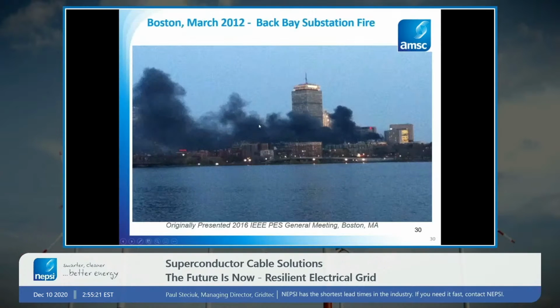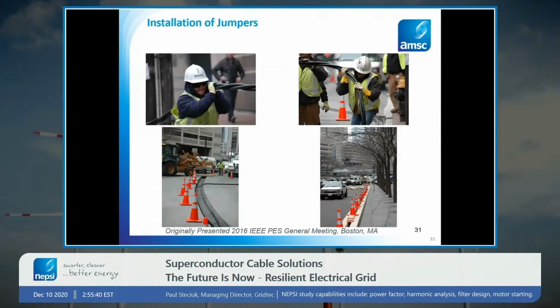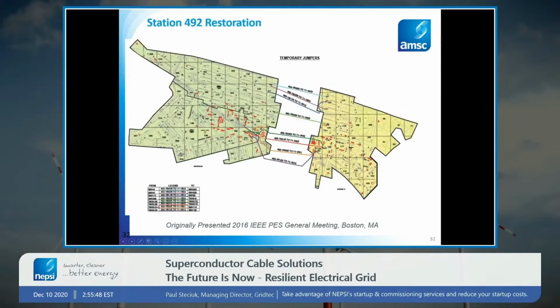In 2012, there was a major fire at a substation in the Back Bay of Boston that had that happen. All of the transmission and transformation into that substation was lost. And so you had a blackout of the Back Bay of Boston. What the utility had to do was run power cables through the streets in order to jumper together the grid that went down to the other grids that still had power. So you had 8 different jumpers run through the streets in order to basically rewire the grid so that they could continue to serve load. It was an amazing achievement. It was an emergency achievement. They managed to do this in 2 days. They were able to jumper things together. But it was obviously a difficult thing to do and something they never want to do again.